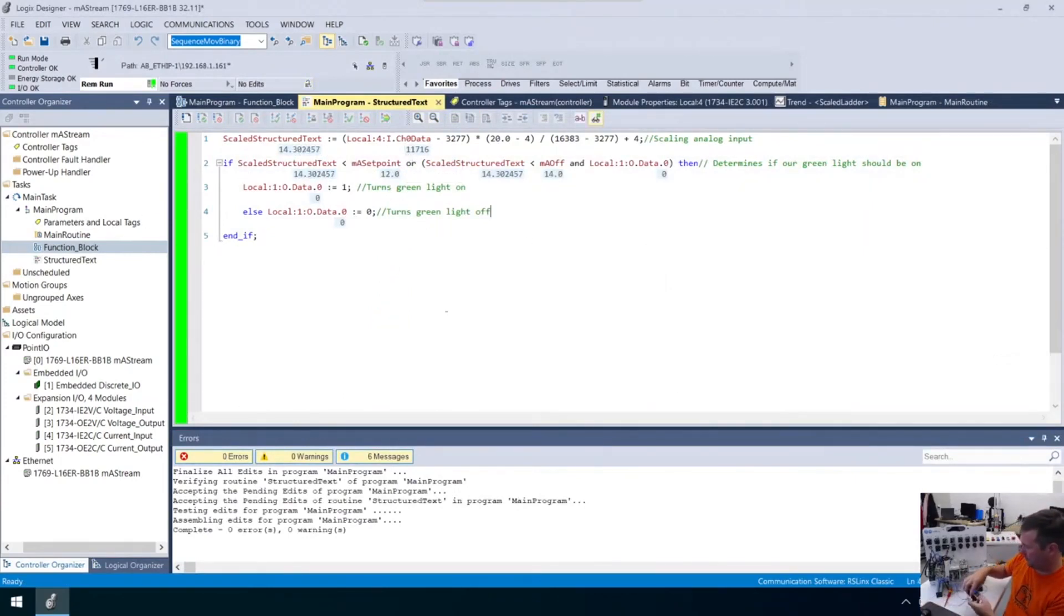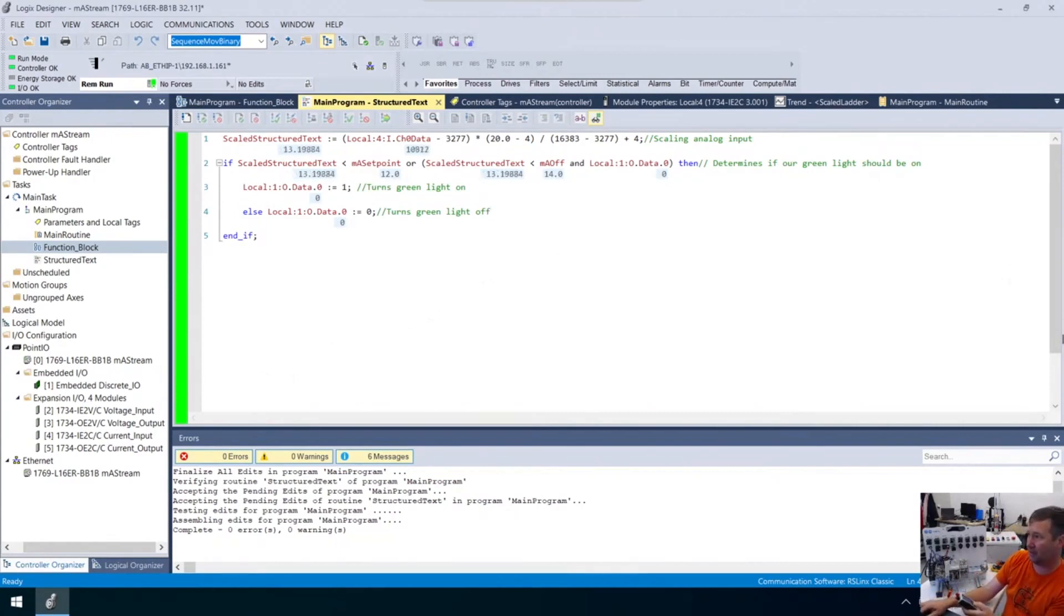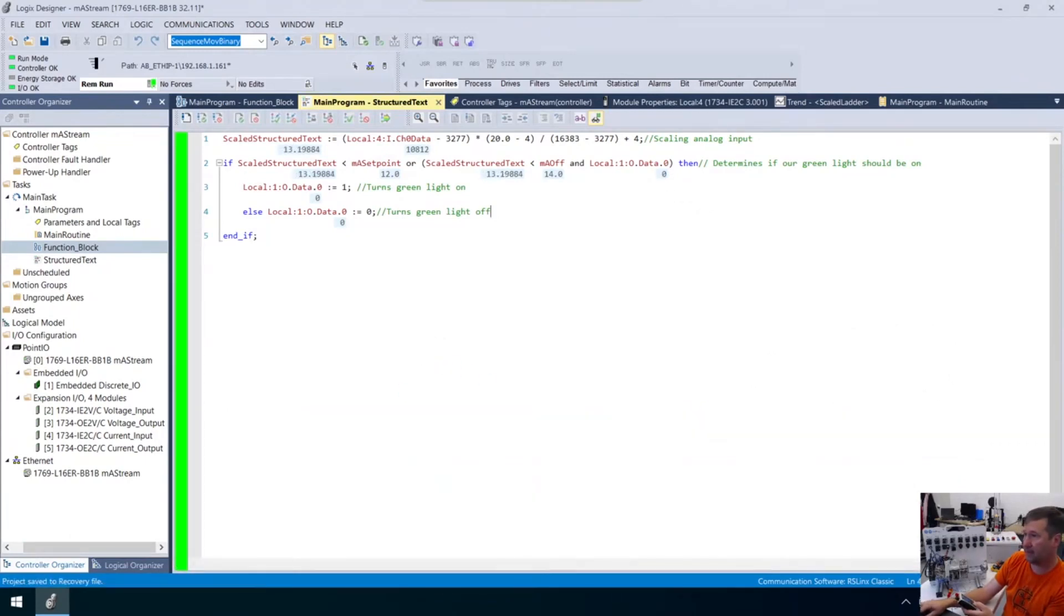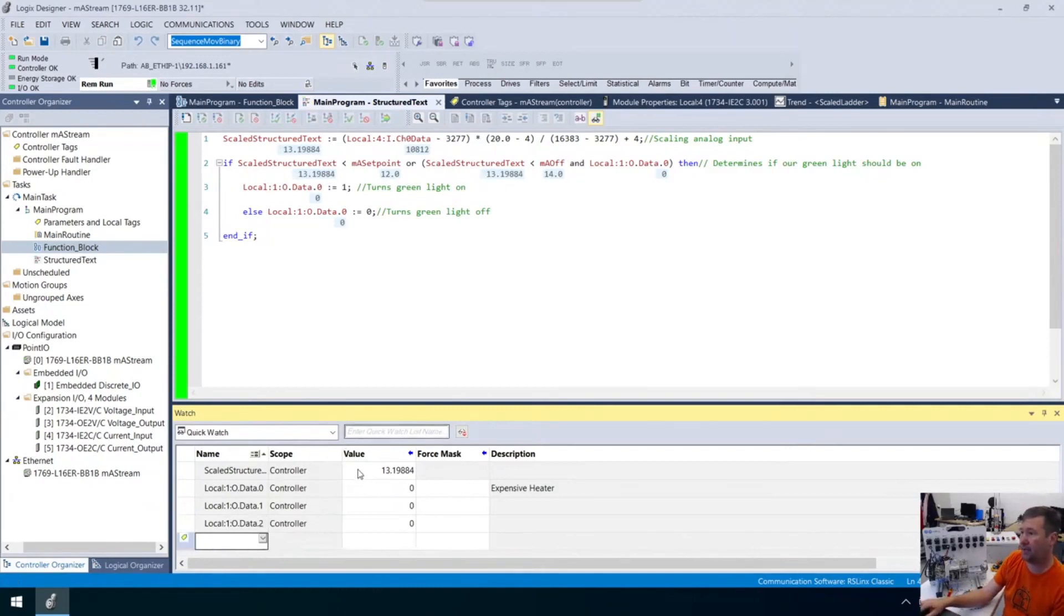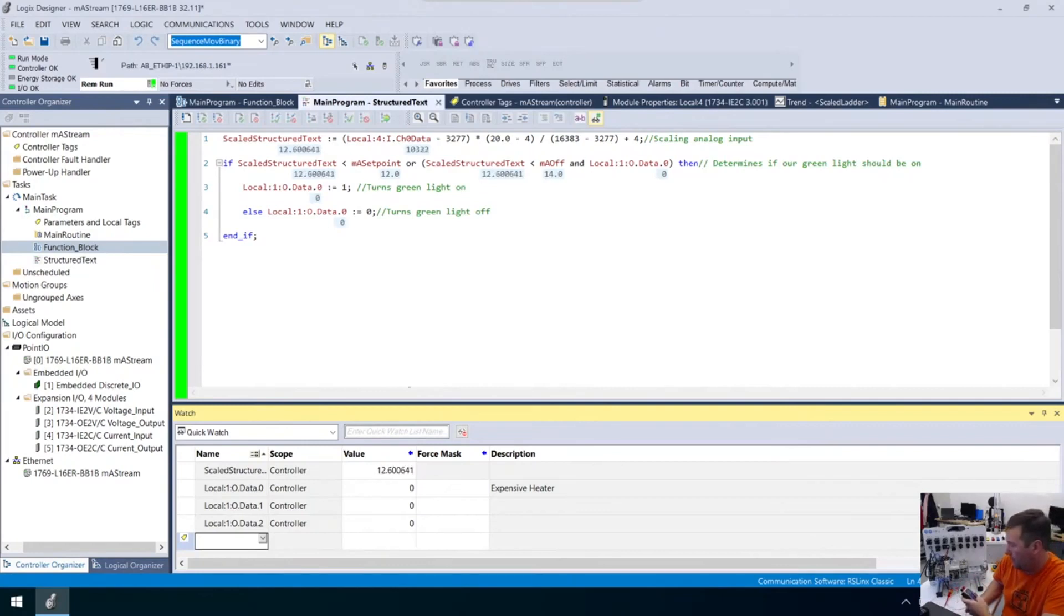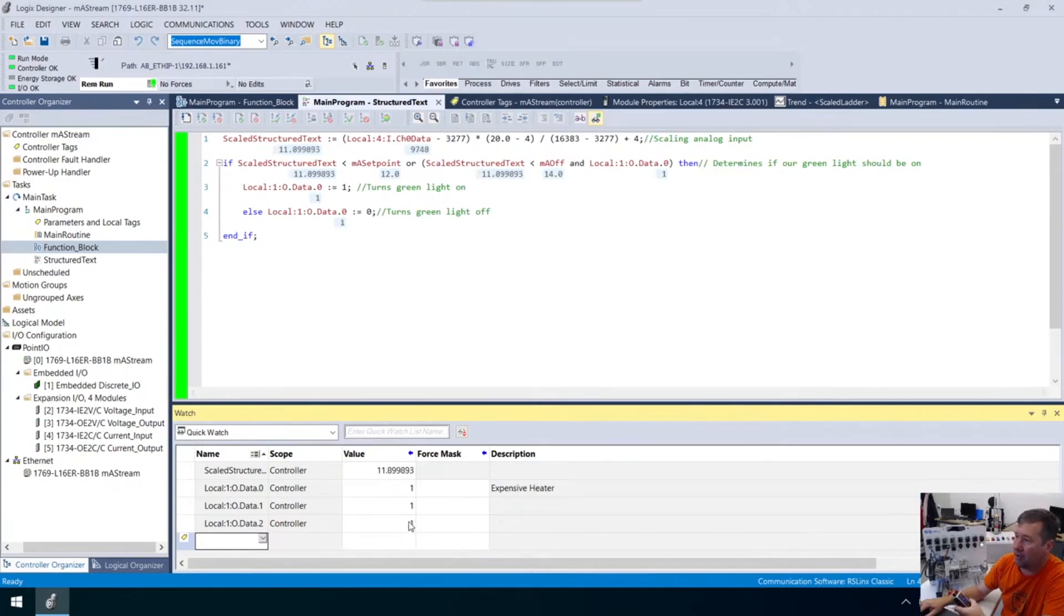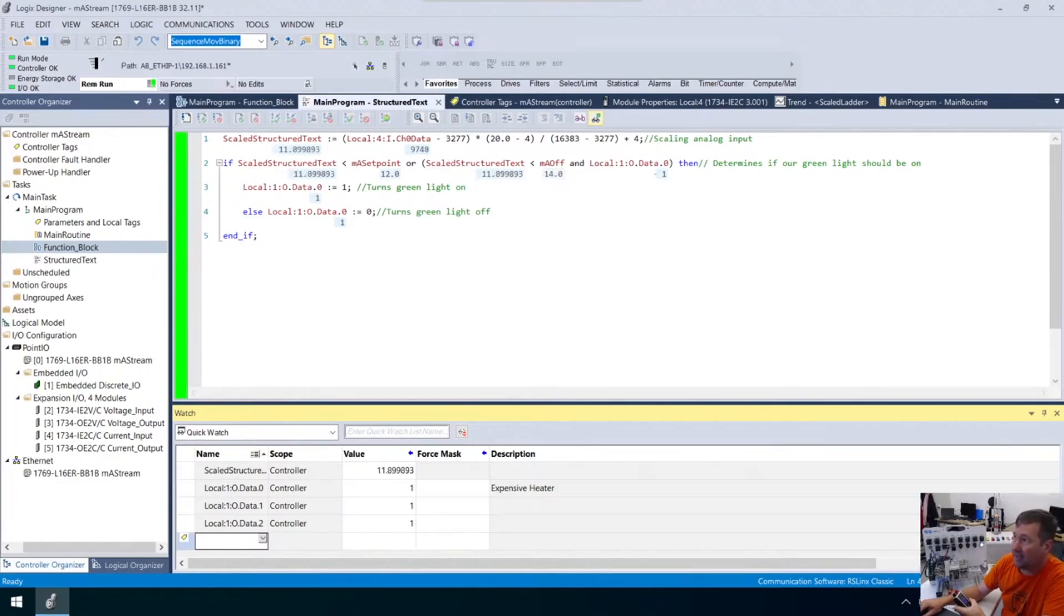Let's see if this works. So we're going to go down to 12 and we should see, well, one, we should see green light come on. Then also right here, we should see this turn to a one. And also if we bring our watch window back, where did our watch window go? Did I close that? I think I did. Yes, I did. Let's go view watch and then let's add five since we did use five for the function block. So they're all off. I'm going to bring this down to 12.1. And okay. And so this is looking for it to be less than 12 and it's off. And we see all of them are off here. We'll drop it to 11.9 right away. All of these come on and we can see, yeah, 11.9 is definitely less than 12 or 11.9 is less than 14. That's also true now. And the pump or whatever, the green light is now on. So both of these are true now.